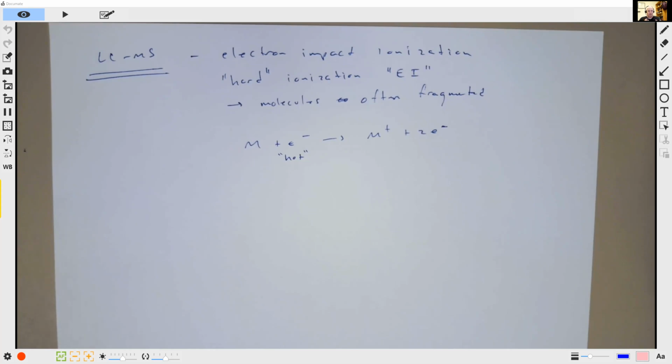If you actively pump this, you have a vacuum pump set up on this, and then you introduce a flow of, say, gas, a leak of gas into this, then the gas analytes will come out as a sort of spray or a jet, right? Then they'll be intercepted by these high energy electrons, and you'll be able to collect the cations from this on a different set of optics downstream.